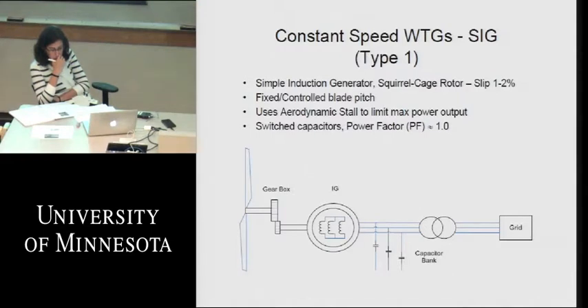And if we get it just about right, we can have the capacitor bank give us a power factor as seen by the grid of unity, or 1. We're not pulling VARs from the grid, and we're not supplying VARs to the grid. And so in that way, we're not doing it in an uncontrolled manner. We're going to see right after this that we want to contribute inductive VARs or capacitive VARs, and draw inductive VARs from the grid for voltage control purposes, if we do it in a controlled manner. But with these Type 1 machines, we really can't do that, and the best we can do is just offset the inductive nature of the generator with a capacitor bank.